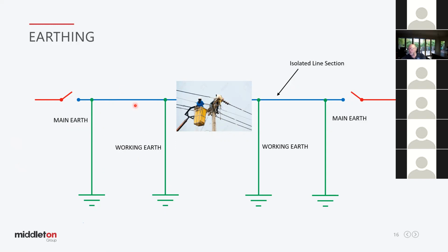The primary purpose of the main earth is to ensure if for some reason this closes or this switch causes energy to be available, there's a very low impedance path for current to flow. And do two things: one, keep the voltage low at that point, and two, make sure the circuit breaker upstream of that device operates. The working earth, its primary reason for being is to ensure that voltages at the location where people are working is maintained close to earth. It also provides a backup for the main earth.